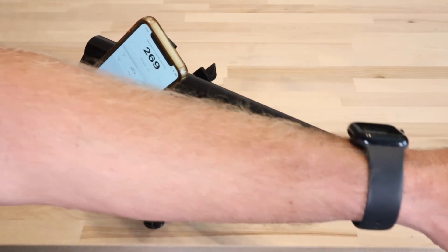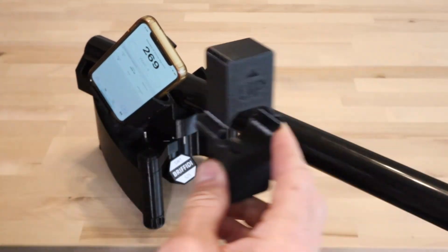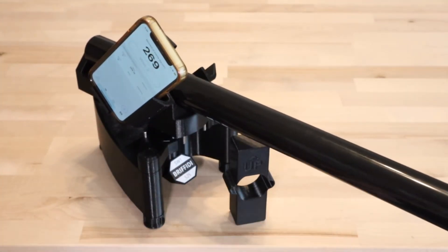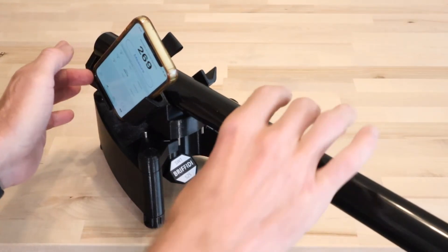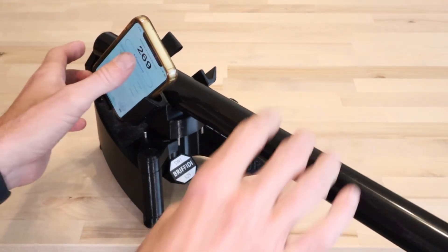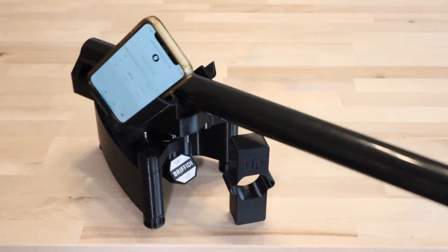Change the calibration rod to the number two configuration by either removing the weight or fully extending the rod. Create a second measurement group by tapping the plus button. Always make sure the rod is tight against the back of the cradle. And in this group, take two measurements.